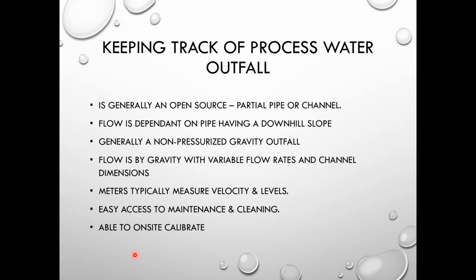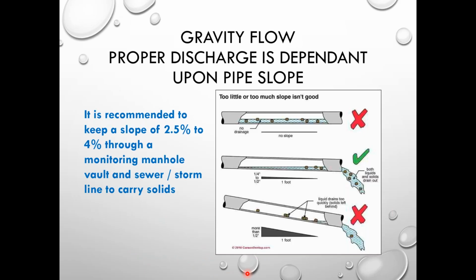Some full pipe, second meter coming in. If you have a mag meter and it needs to be wet calibrated, it has to go back to the factory, right? So they have to take the flow meter out, send it back to the factory, get it calibrated, and have it come back. So many times they'll have a spare meter for when that meter is going back for calibration.